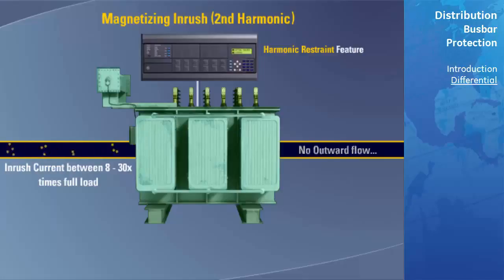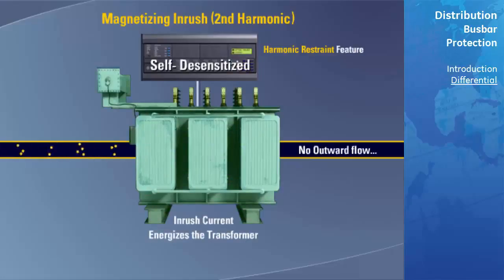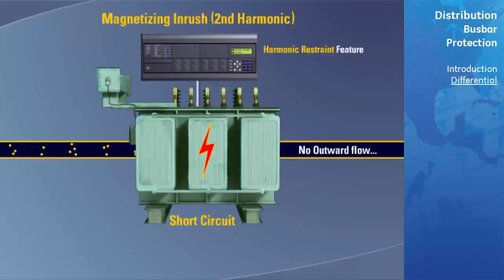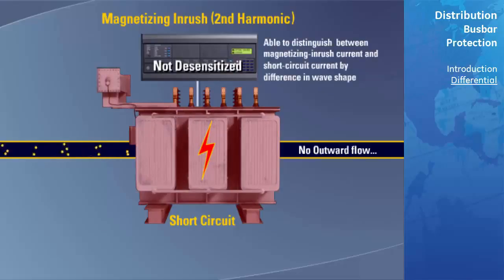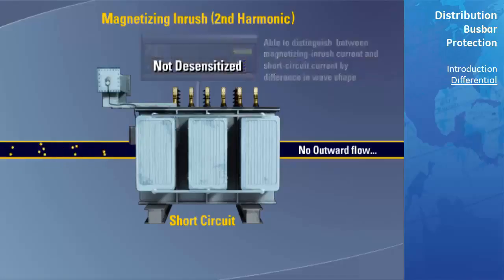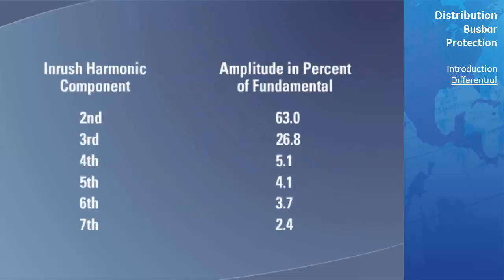Let's take a closer look at harmonic current restraint. The principle of harmonic current restraint makes a differential relay self-desensitizing during the magnetizing current inrush period, but the relay is not desensitized if a short circuit should occur in the transformer during the magnetizing inrush period. The relay is able to distinguish between magnetizing inrush current and short circuit current by the difference in wave shape. Magnetizing inrush current is characterized by large harmonic components that are not noticeably present in short circuit current. A harmonic analysis of a typical magnetizing inrush current wave was as shown in the accompanying table.